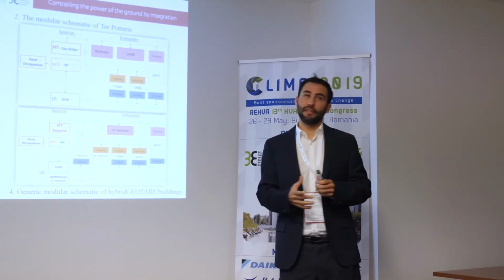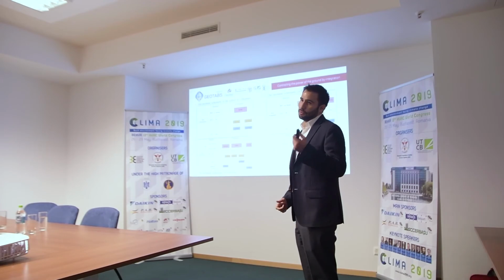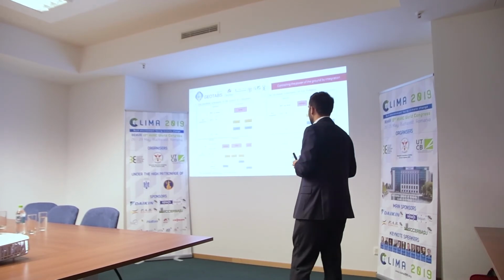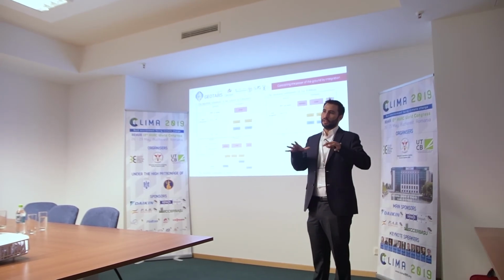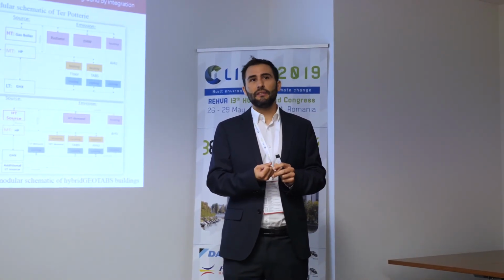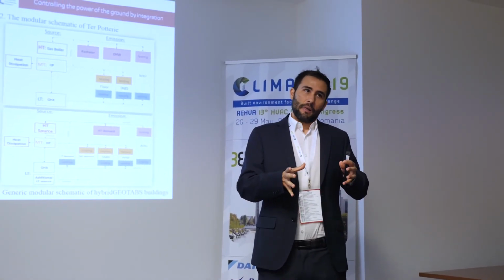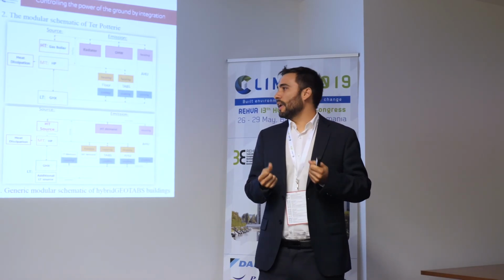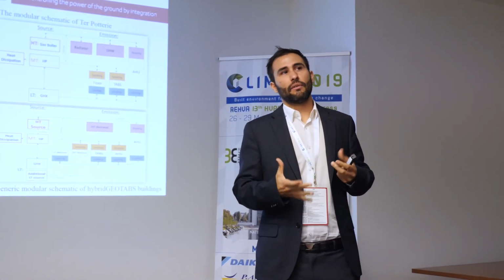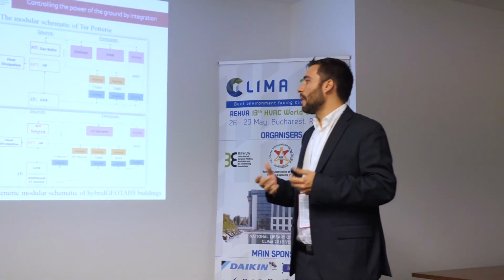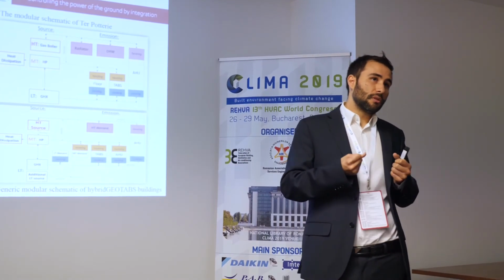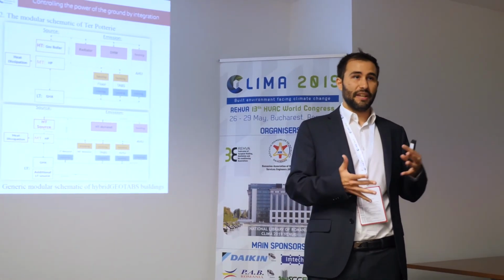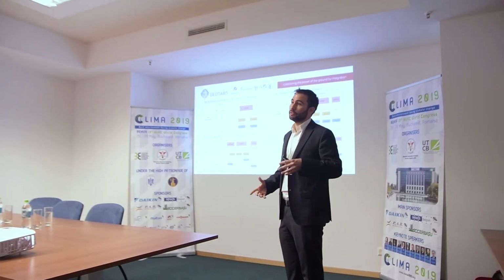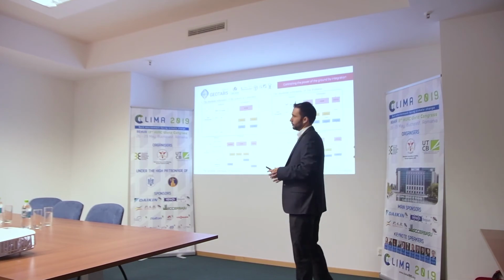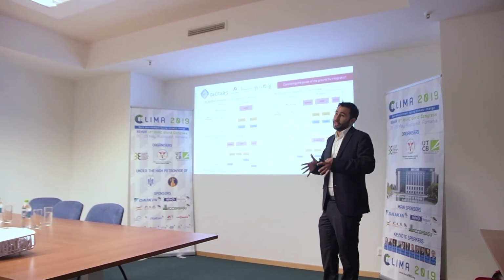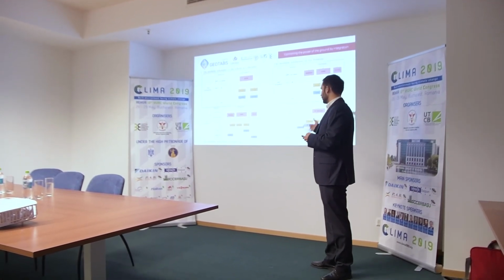In the part of the geothermal heat exchanger, the design is very important for two main reasons. The first reason is that the geothermal heat exchanger has an important initial cost, so the design is very important. It's very important to design a very optimized borehole field, taking the maximum energy that you can from the borehole field, sizing in a good way. And on the other hand, we have to guarantee that we are going to provide the energy that the building needs during the whole operation, during the life of the building. So it's very important for the guarantee, and it's very important for reducing the initial cost, but with a very good operation of the whole system.